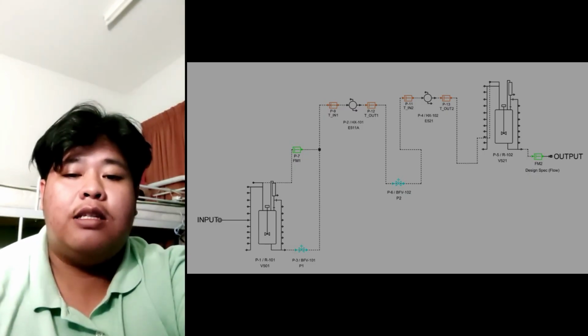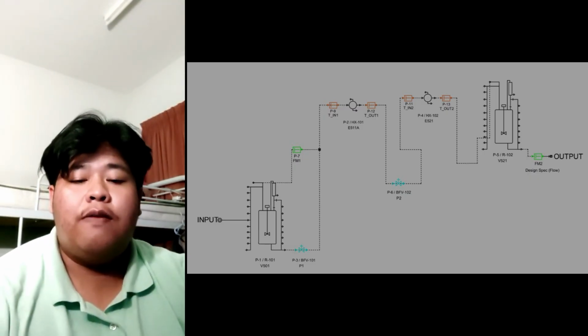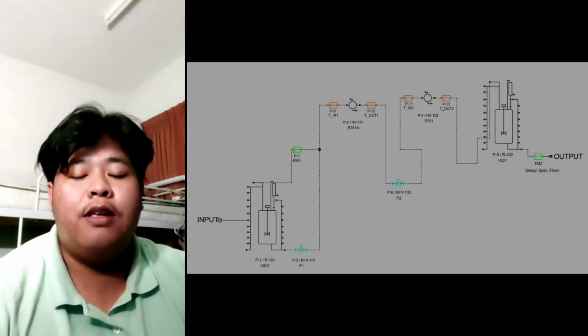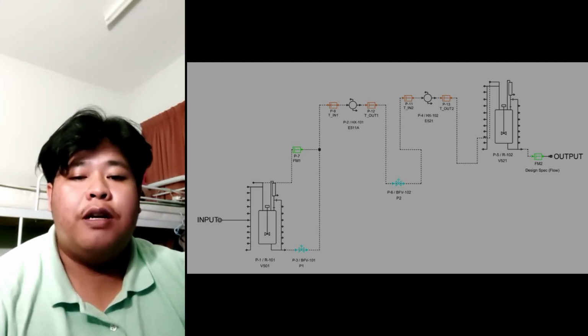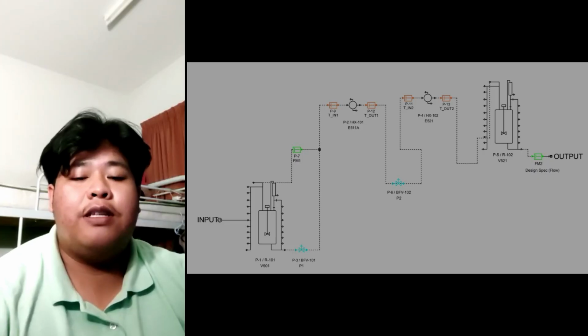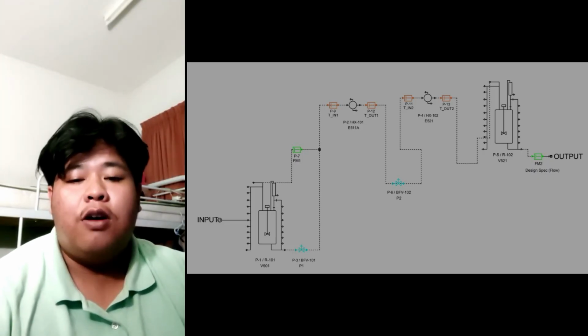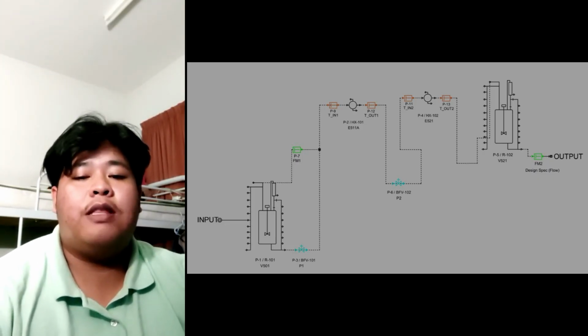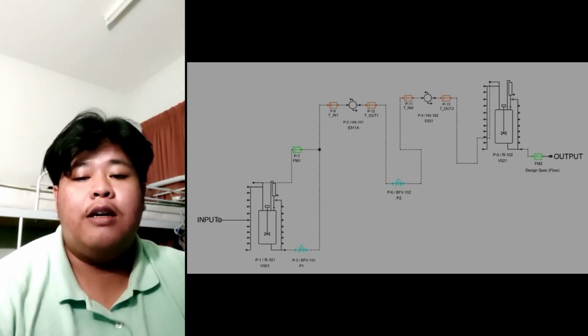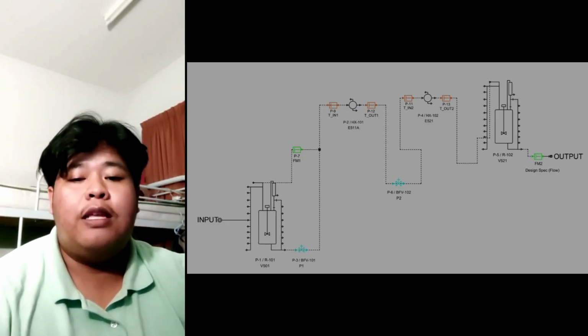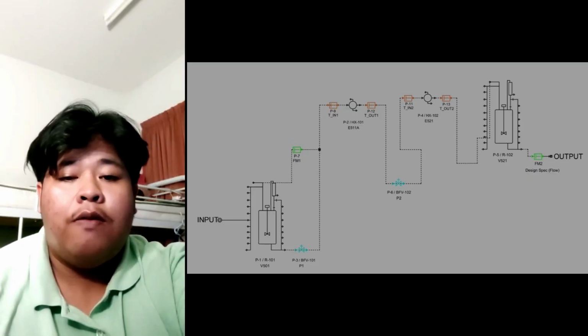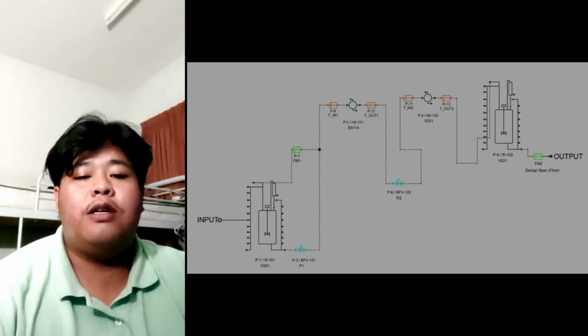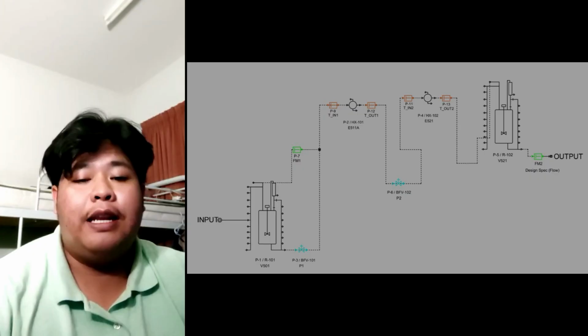The third is safety. The valves BFV-101 and BFV-102 are equipped with spring return actuators. This is a critical feature in the event of a power outage or system failure. The valve will automatically snap into a safe position, either fully open or fully closed, protecting the equipment and personnel. Finally, this setup shifts us from reactive to predictive maintenance.